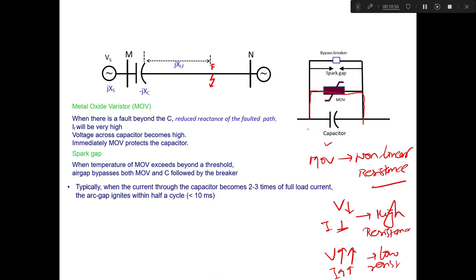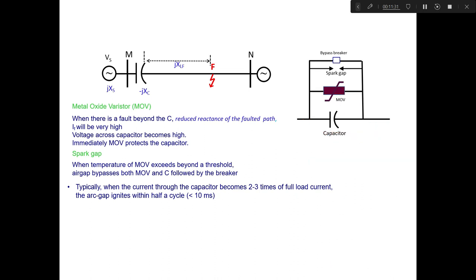During normal current flow, all current flows through the capacitor and ideally no current flows through the MOV. However, in case of high current, the capacitor is bypassed through the MOV once the voltage across the capacitor bank exceeds its rated level — for example, 53 kV. Only the current corresponding to that voltage level will continue to flow through the capacitor bank, and the remaining current passes through the MOV.